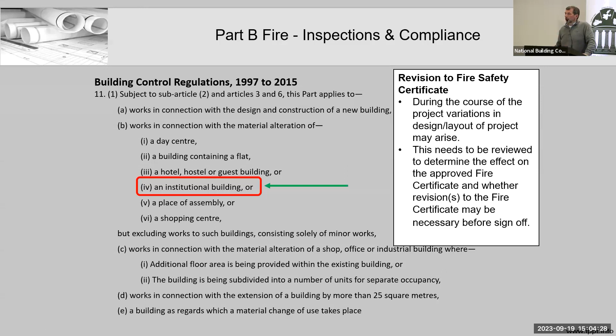When looking at the project as a whole, there may be a need for site-specific fire testing. It depends on the project, but for example we may have very large, complex, and detailed service arrangements requiring fire stopping, some going above and beyond the manufacturer's requirements. If I have a 450 millimetre diameter pipe, that's not in any standard fire stopping brochure as to how it can be achieved, so we may need to get something fire tested to demonstrate compliance.